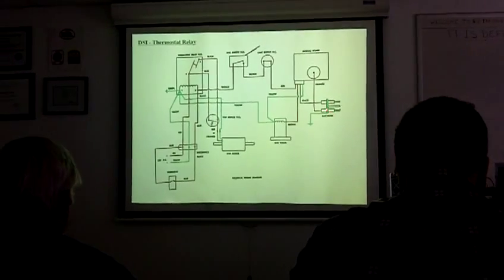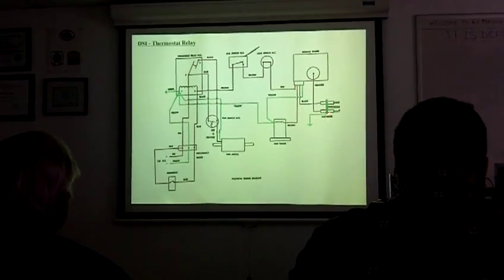It could be a cracked electrode. Your sense electrode could be cracked. It could be rusty connections on any of those screw connections there that you'll see.